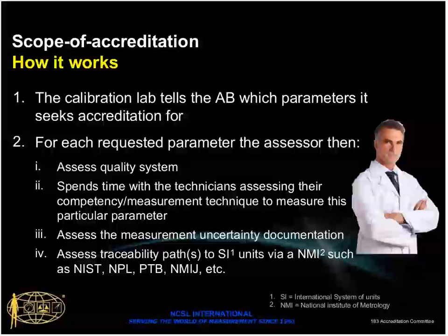So you need to consult the schedule of accreditation, as it's called in the United Kingdom. It's called the annex to the certificate in the case of many of the European accreditation bodies. But don't just ask for the certificate, ask what they're accredited for. Again, whether or not you're going to use accredited services. When we assess laboratories, we assess that they have documented procedures and staff competency for each individual measurement that they're accredited for, as well as having the traceability of measurement, which is required to be accredited.